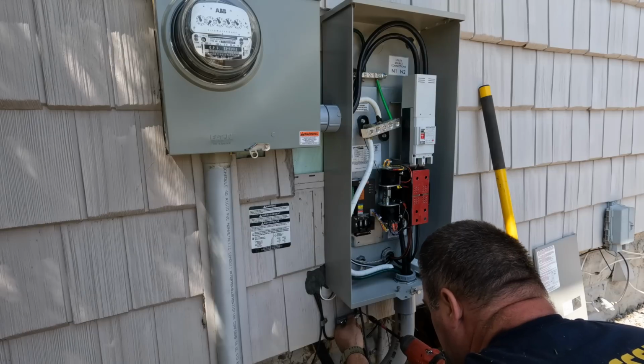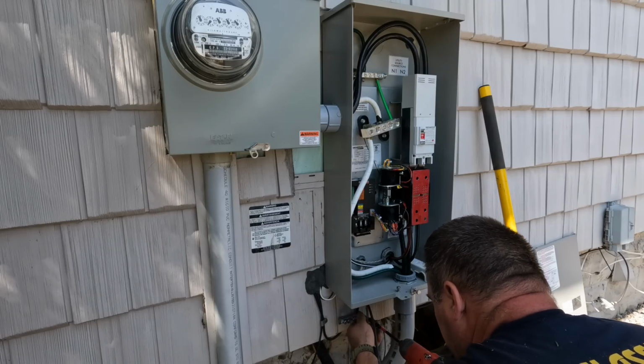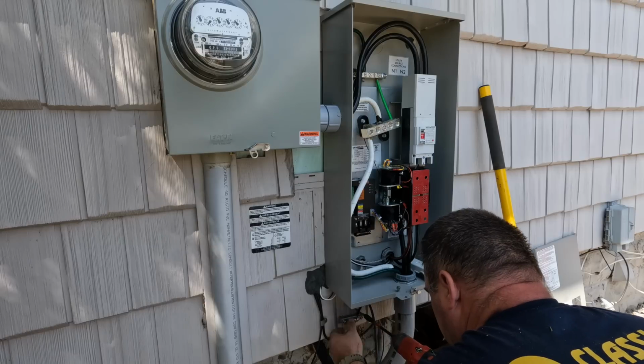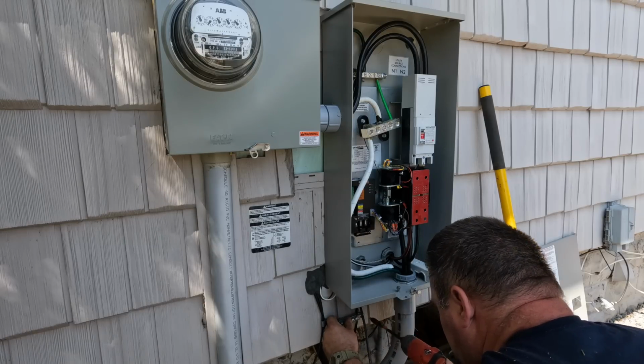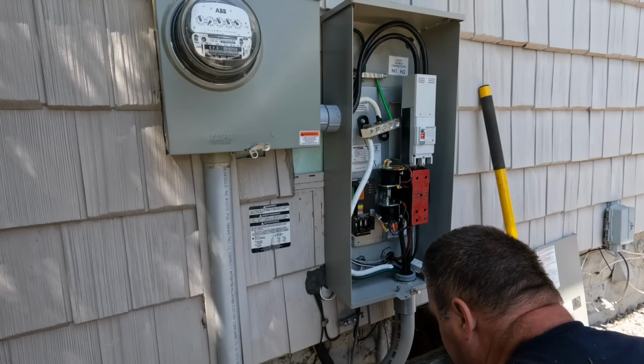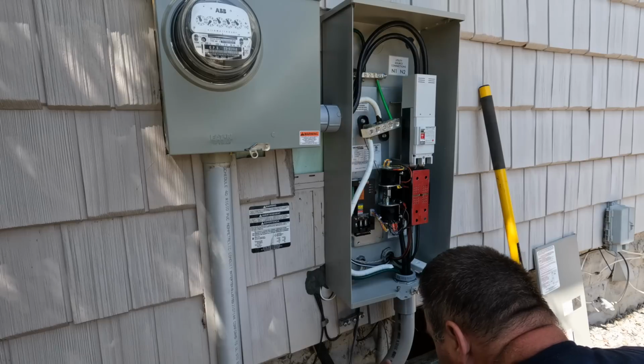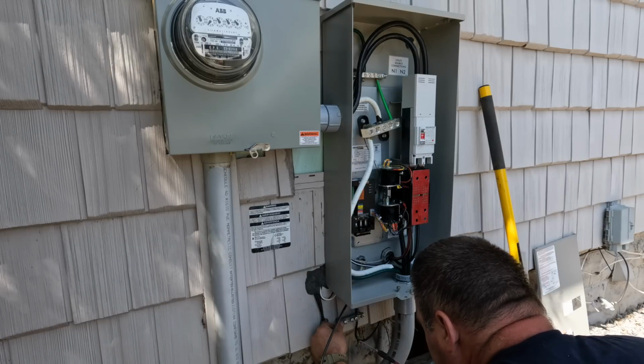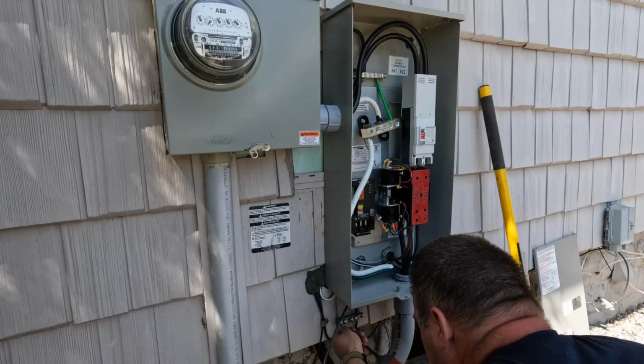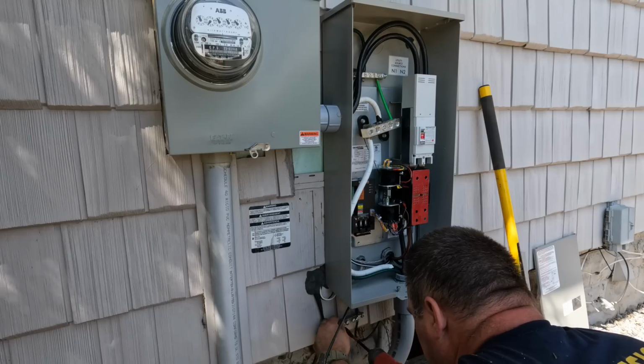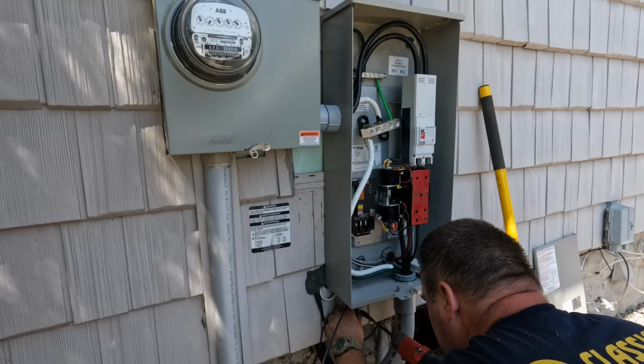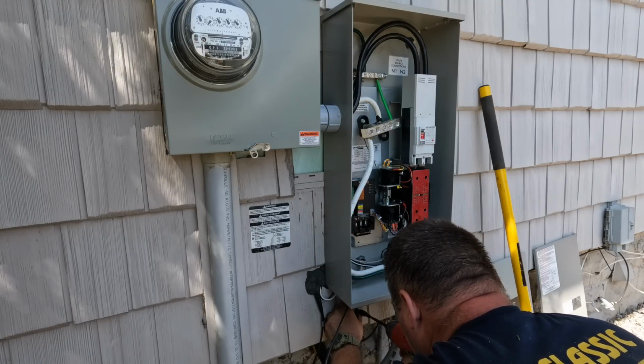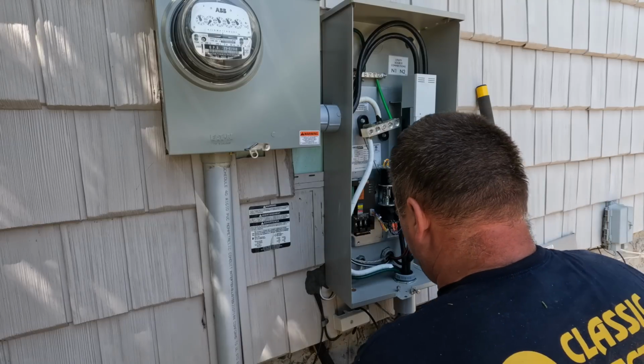So here, that's the bonding bridge that I'm attaching. I like to run the wiring from the ground rods directly through it, and then I'll enter the enclosure right underneath where I'm working here. Both of the conductors, both grounding electrode conductors, the ground rods and the water main, will come through the same plastic connector at the bottom and attach to the ground bar inside the automatic transfer switch.